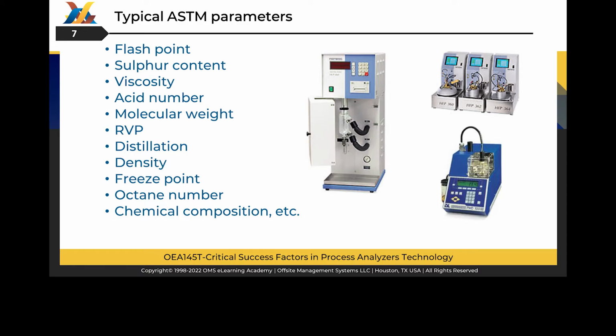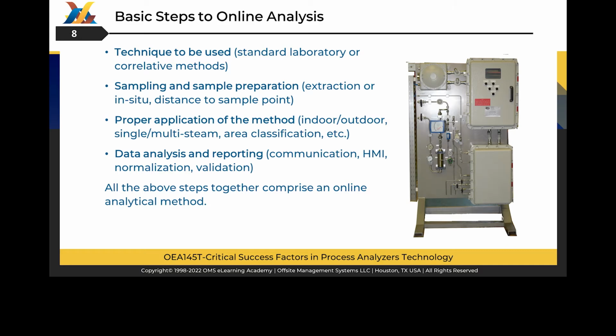For every one of these methods, many different types of laboratory instruments can perform offline measurements of samples from the process. Basic steps to process analysis include choosing the analytical method, sampling and sample preparation, proper location and housing, communication to control system, and reporting. Process analyzers' sample probes and sample transport lines are designed to ensure representative and rapid sampling, avoiding a possibility of contamination or dead volume. Typically, complete integrated analyzer systems and all related services can be provided by experienced system integrators. Process analyzer systems are installed in the unique analyzer houses, including air conditioning, power distribution, lighting, termination and junction boxes, gas and flame detection, appropriate piping, and wiring.